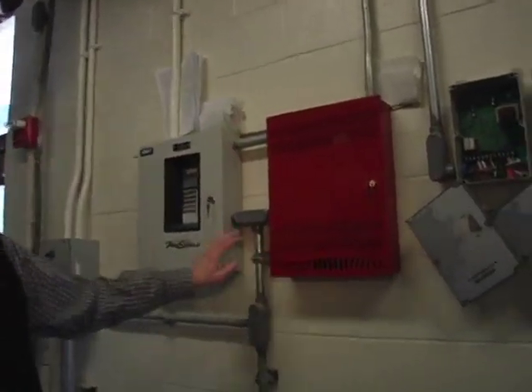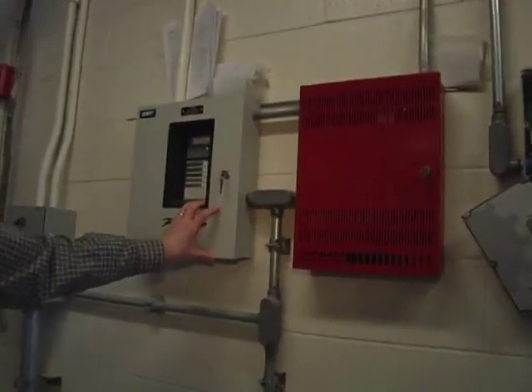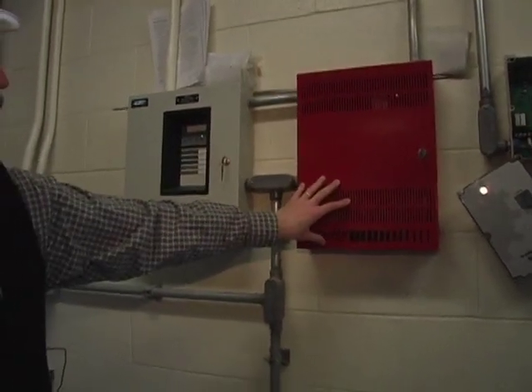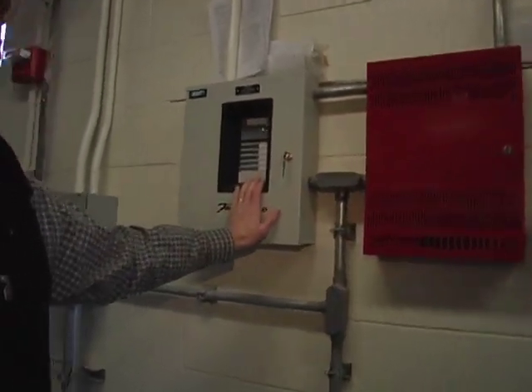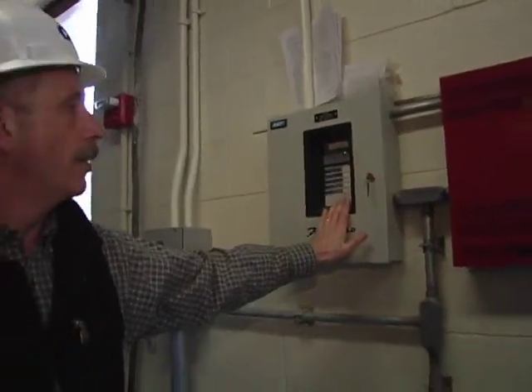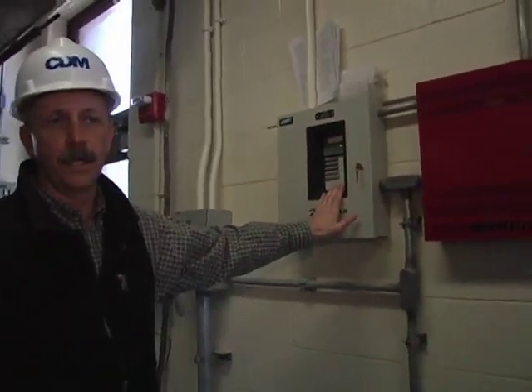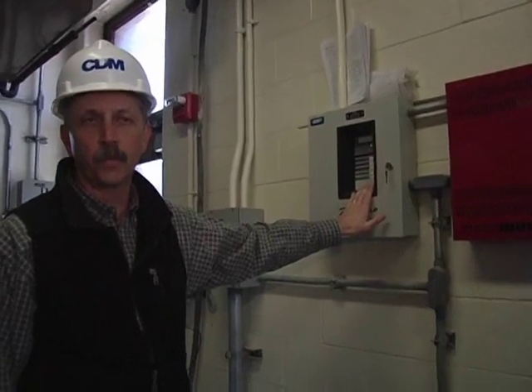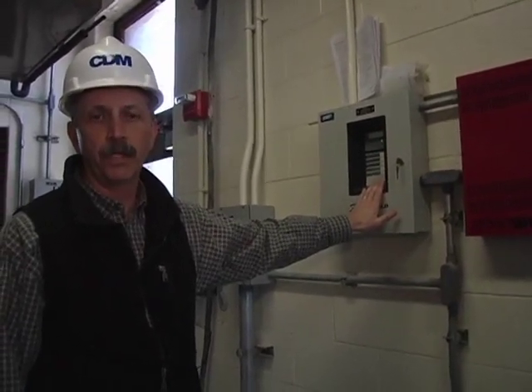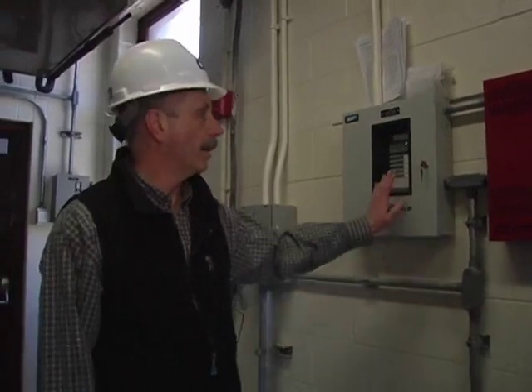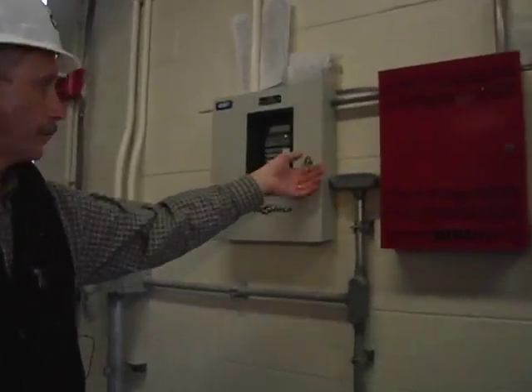Beyond that are the two alarm panels here. It's a power supply panel which feeds the alarm panel for the gas detection system. There are detectors throughout the building, as well as outside of the building on the aerated grit channels. The ones within the building are fed back to this panel, so if you do have a high explosive level within the building or a high hydrogen sulfide level, that indication will come back to this panel.